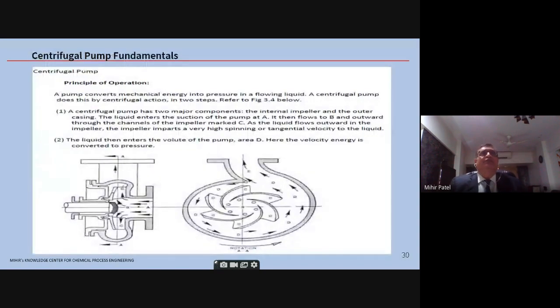Then we come to centrifugal pump fundamentals. As you can see in the diagram, the fluid enters the suction on the left-hand side. The suction nozzle is there, then it goes through the impellers, which basically translate the velocity into head, and then it discharges at the outlet. So this is a typical centrifugal pump. Impellers are of different types. I'll come to that also.